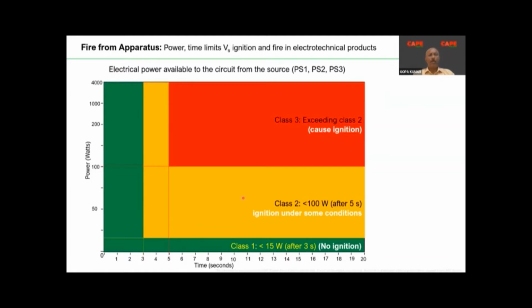Similarly, class 2 is a power source with which the amount of power is limited to less than 100 watts in 5 seconds. In the class 2 case, ignition may occur. It depends on the environment, how you are placing the equipment, how far the other equipment are, and what kind of flammable things you are keeping near to that. And power source class 3 is very clear. This will create a fire if there is an ignition, so it is exceeding the limits of class 1 and class 2.